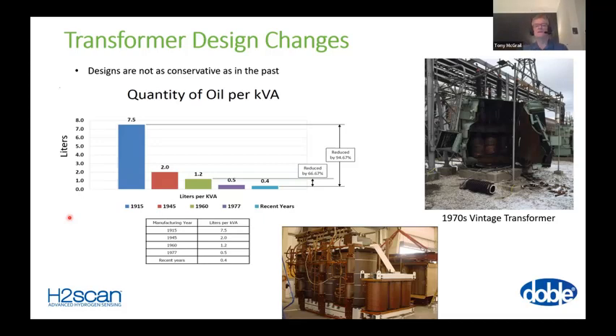The transformer at the bottom in the middle is the guts of a transformer after it had been taken away from site after it had failed. It was very difficult to inspect internally, but you can see the three main windings off to the left. And on the right, we've got what's called a preventative auto, which helps regulate the voltage on the tap changer. Within that preventative auto, a brazed joint had come apart, and that had led to huge amounts of heat generated at the poor joint. We had temperatures on the tank next to that in excess of 200 degrees C. That was a transformer we tested ad nauseam, to quote Leon from earlier. We got lots of information, said we can't fix it on site, take it back. They fixed it, put it back in service, and away they went.